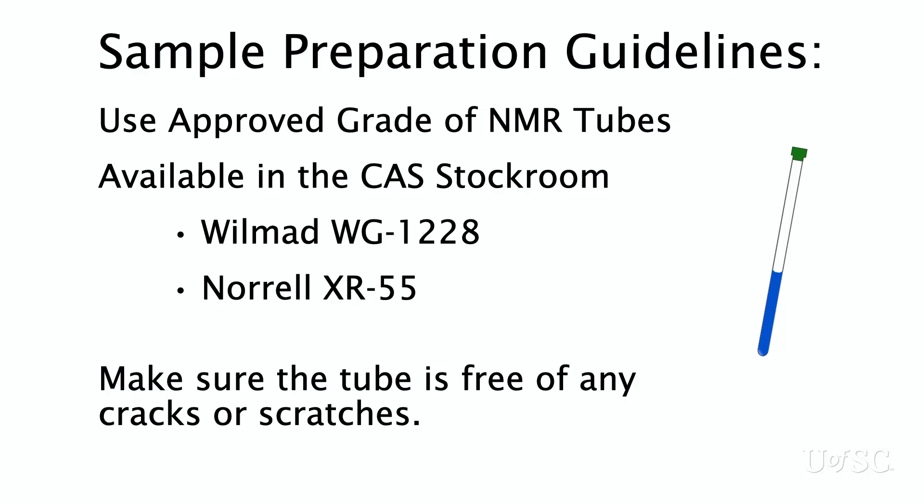The minimum grade of tubes are either Wilmad WG1228 or Norrell XR55. These are considered economy grade tubes but they have specifications for straightness and diameter that are safe for our instruments. These tubes are available in the CAS stockroom.